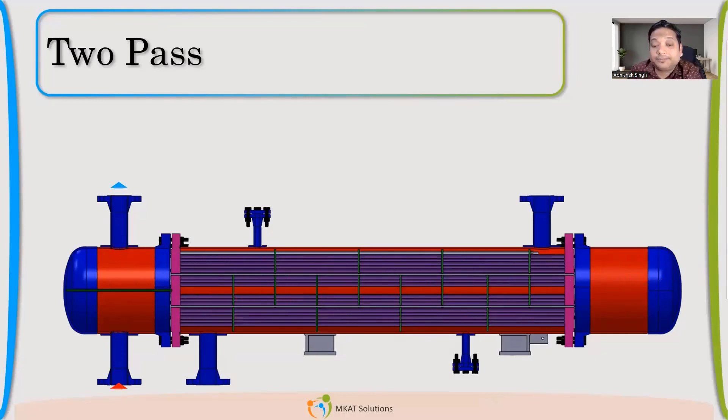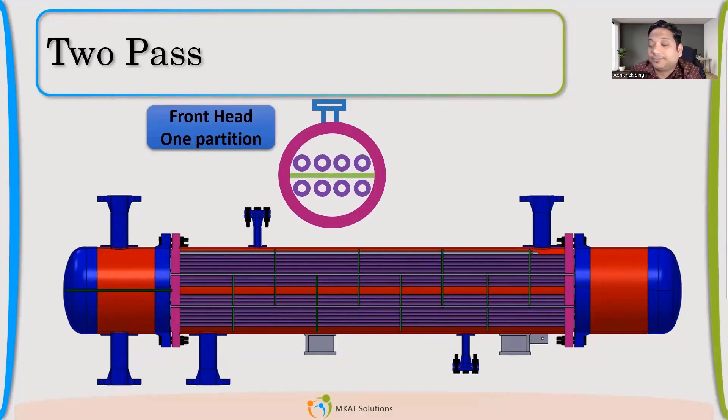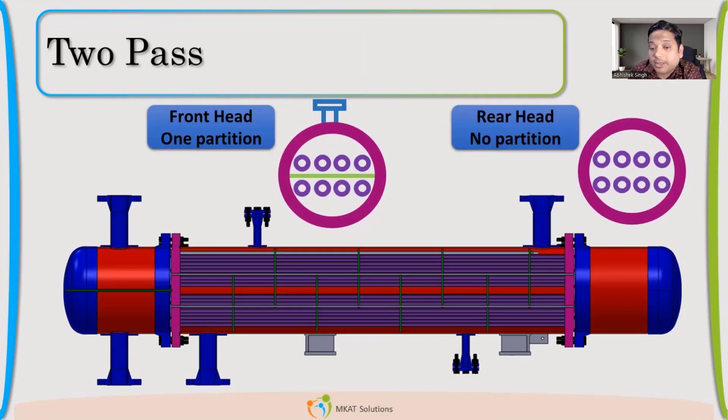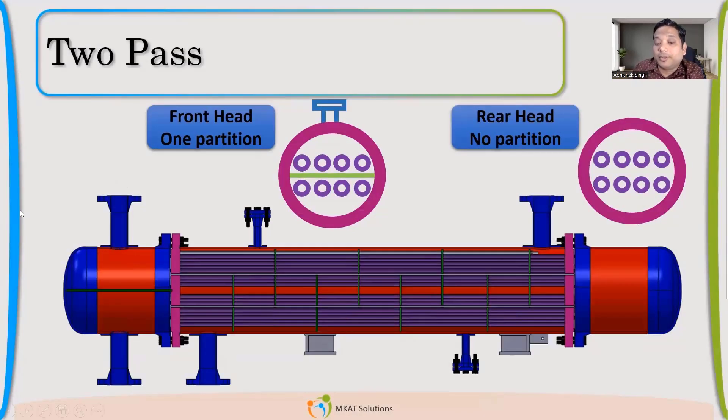How will be the construction? This is the front side tube sheet. We'll just divide. Let us assume there are eight tubes. So we'll divide in two. In the first four, there will be inlet. All the fluid will be going inside from this. And then it will come out from the other side. There is no pass partition in the rear side. So it will enter in the next four and then come out from this side. So this is how it will flow in two pass.